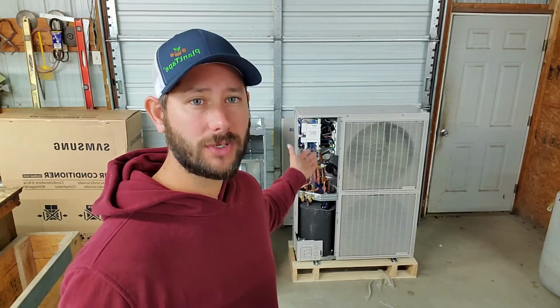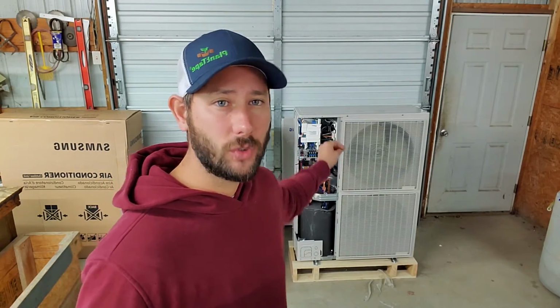Max overcurrent protection. The breaker size that you need for this equipment is a double pole 35 amp breaker. That is all. To power this equipment, 35 amp breaker. Minimum circuit amps is 26 amps. So very minimal, especially compared to a heat pump that needs a 30 amp just for the heat pump and then a 60 amp for the heat strips. So that's a really, really big reduction in the amount of breaker size and power required to power a heat pump. Operating temperatures are way better, piping connections way better, wind baffles offered as an accessory so that you can have an even colder temperature outdoors that you can operate in the cooling operation.